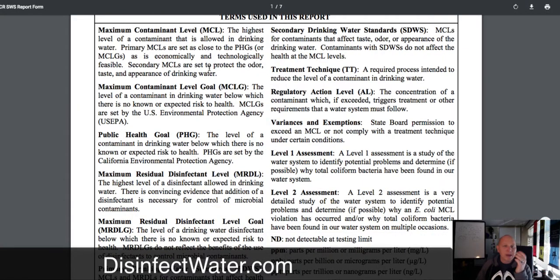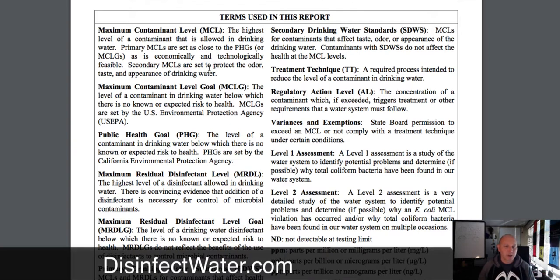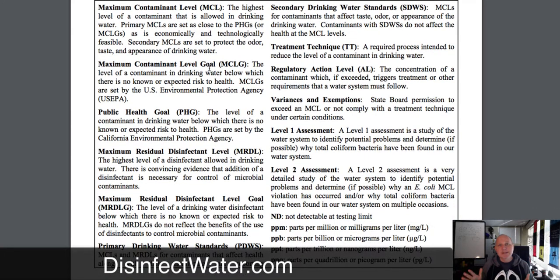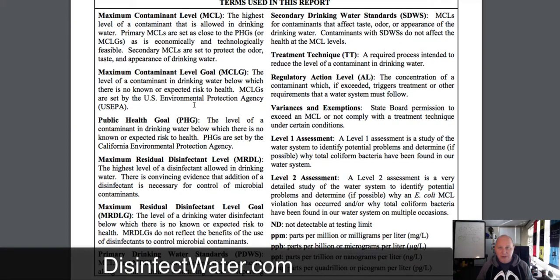The maximum contaminant level is the highest level of a contaminant allowed in drinking water. For water to be safe, you can't have more than this amount. Then there's the goal — the MCLG — which is where people want to get to. Public health goals are similar. Residual disinfectant level refers to disinfectants that can still remain in the water. There's also the maximum residual disinfectant level goal. Primary drinking water standards are what utilities are measured on. The regulatory action level is a threshold — if exceeded, they have to take corrective action.